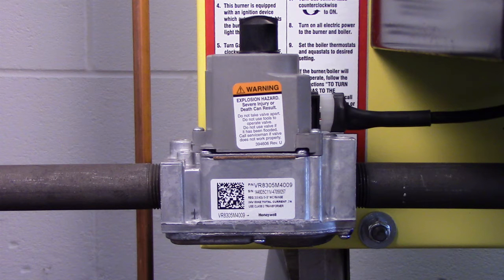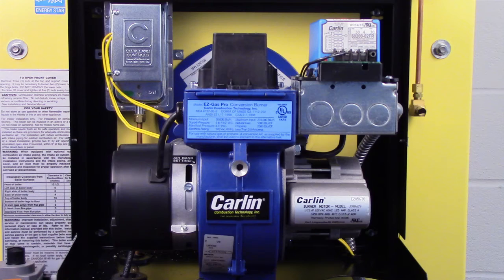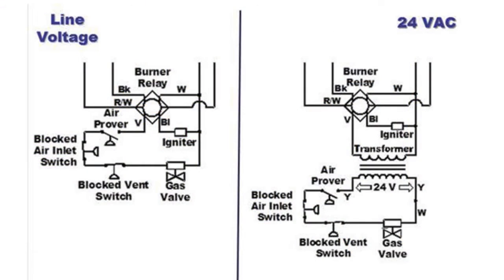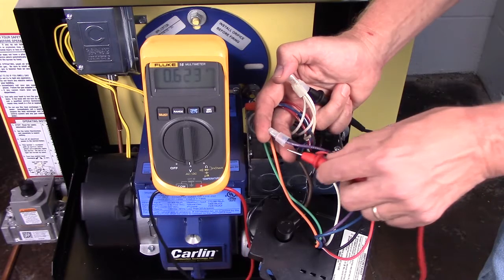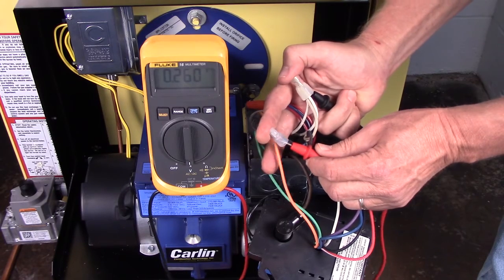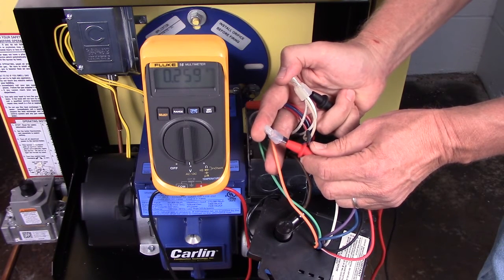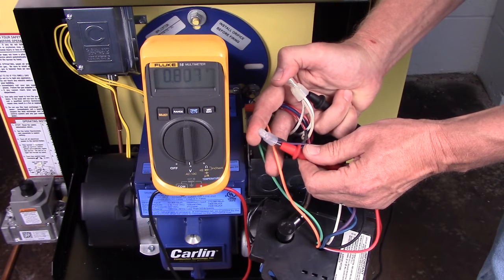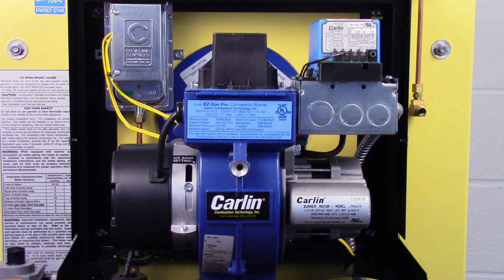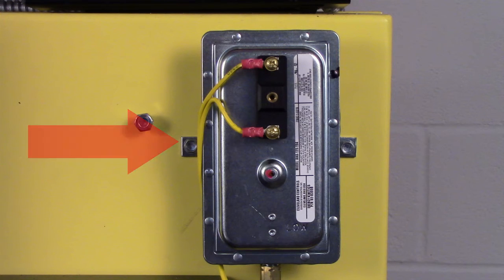If correct voltage is not present, use a voltmeter to trace the gas valve circuit. Burners with a 24 volts AC gas valve have a 24 volts AC transformer that is supplied with 120 volts AC from the primary control's violet wire. Measure voltage with a voltmeter at the primary control's 120 volts AC output on the violet wire to the transformer. Next, check for 24 volts AC from the transformer, then through the burner airflow switch, the blocked air inlet switch, and the blocked vent switch to find the break in the circuit.